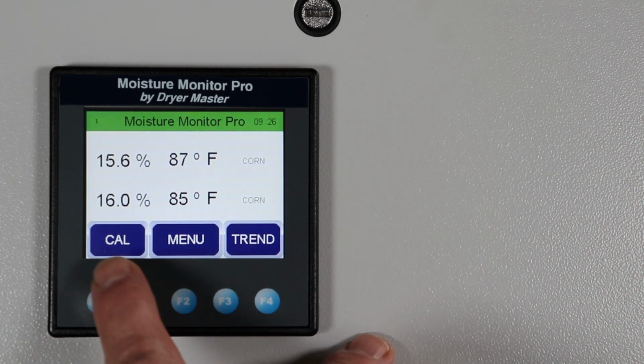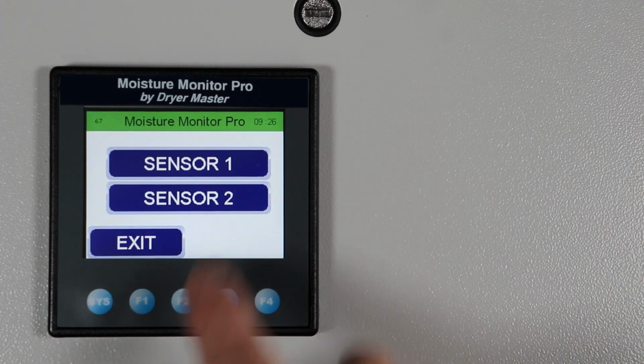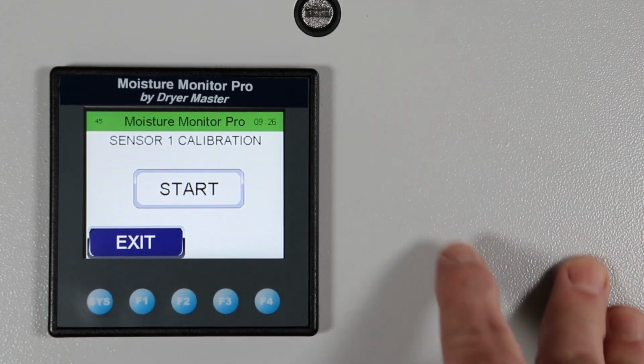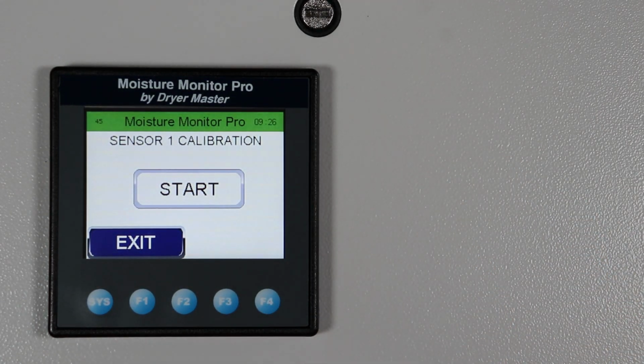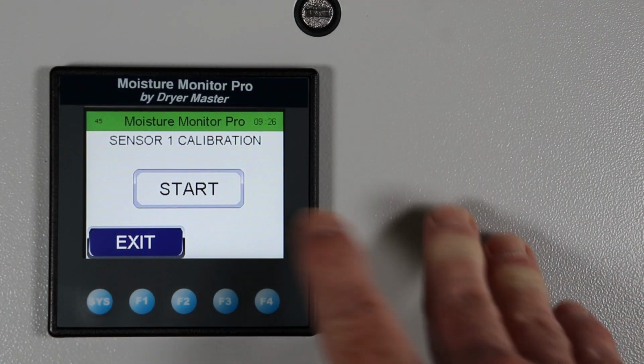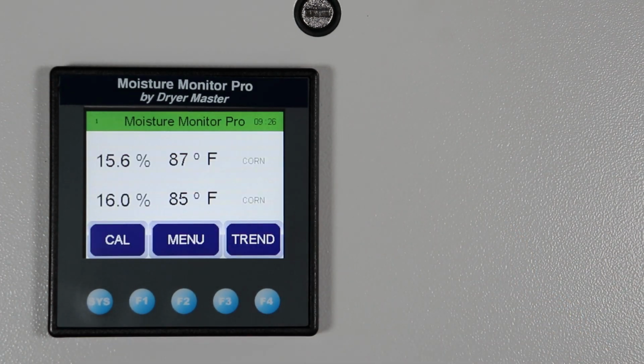Okay, so we're going to calibrate sensor 1. Now we don't have a calibration button right here, so we're going to use the virtual one here. So we start. And now what's supposed to happen is you go out and you take a sample. And the idea is that you take a sample over 30 seconds. And the Moisture Monitor Pro will also collect information for the next 30 seconds while the calibration button is flashing. At the end of that 30 seconds, it'll calculate an average of what its moisture was.